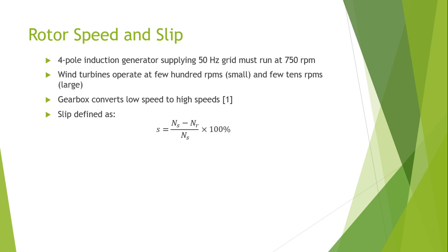If the speed of the rotor is equal to the synchronous speed, then no relative motion occurs between the stationary rotor conductors and the main field. No electromotive force is induced in the rotor, and zero current is generated in the rotor. The electromagnetic torque is not induced. Thus, the speed of the rotor is always kept slightly less than the synchronous speed.